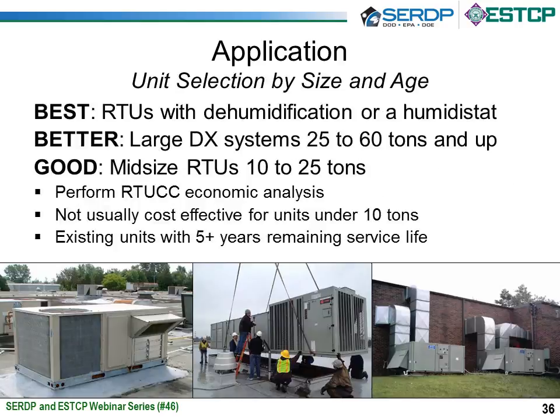Selection of which units to apply to. The best applications, the ones that you really want to look for, are RTUs with some sort of active dehumidification, or a humidistat is a good way to tell if it has active dehumidification. Better is large DX units, 25 to 60 tons and larger, and good is mid-size RTUs from 10 to 25 tons.